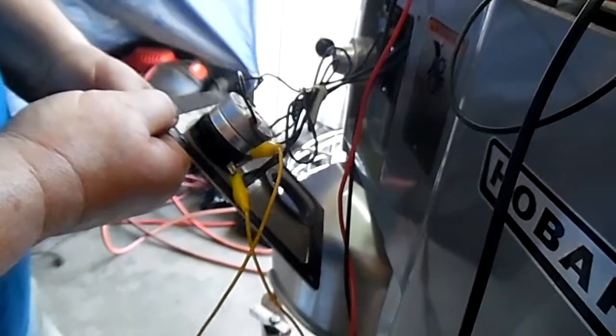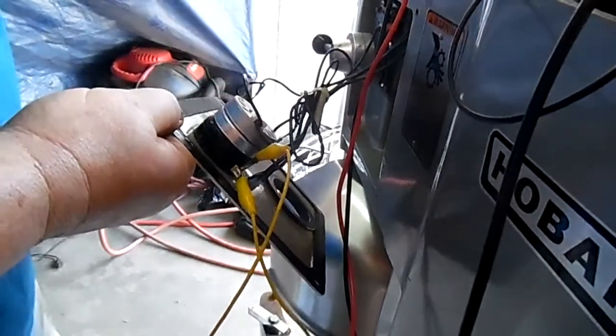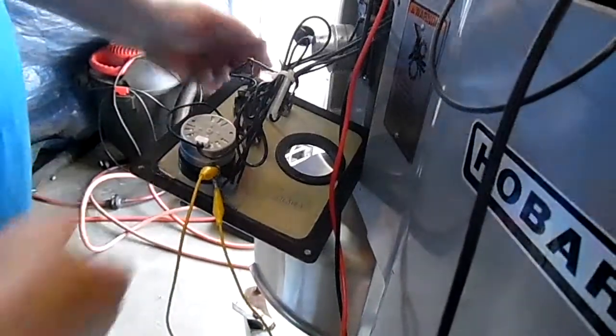If you think the timer's bad and you turn it to hold or five minutes and it won't work, you jump it. If it works, you know your timer's bad. I'm going to leave the jumper on for a couple other tests.